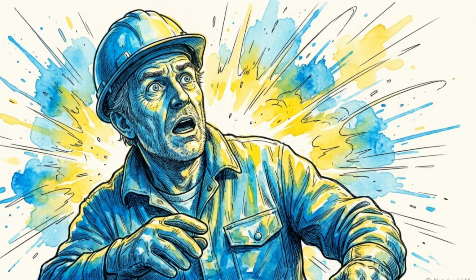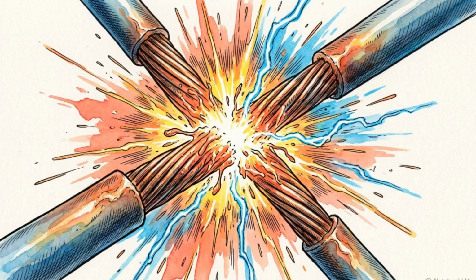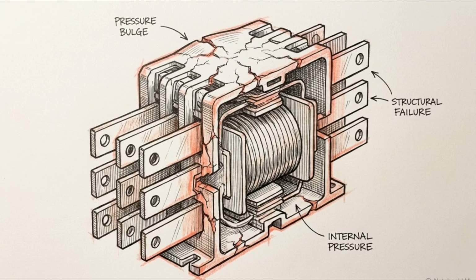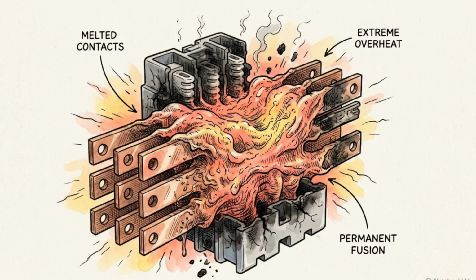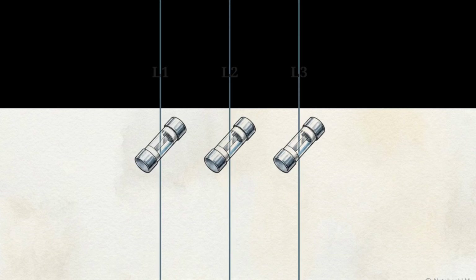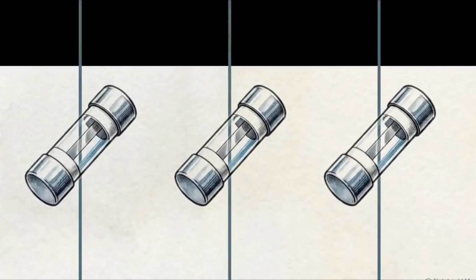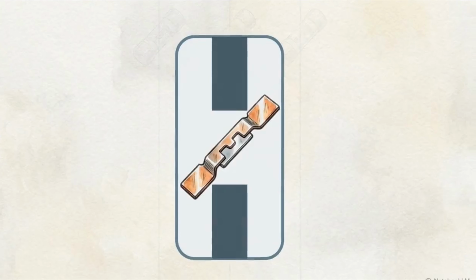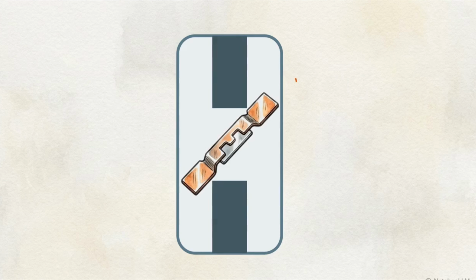But isolation does not protect against a sudden fault. If crossed wires create an instantaneous short circuit, a massive flood of current will tear through the system. The contactor cannot stop this volume of electricity. The heat of such a surge would simply melt its internal components and fuse the contacts permanently shut. To prevent this, we move to the top of our schematic, placing three fuses at the very origin of the power supply. Zooming in on one of these fuses reveals a precisely calibrated strip of metal bridging the electrical path.